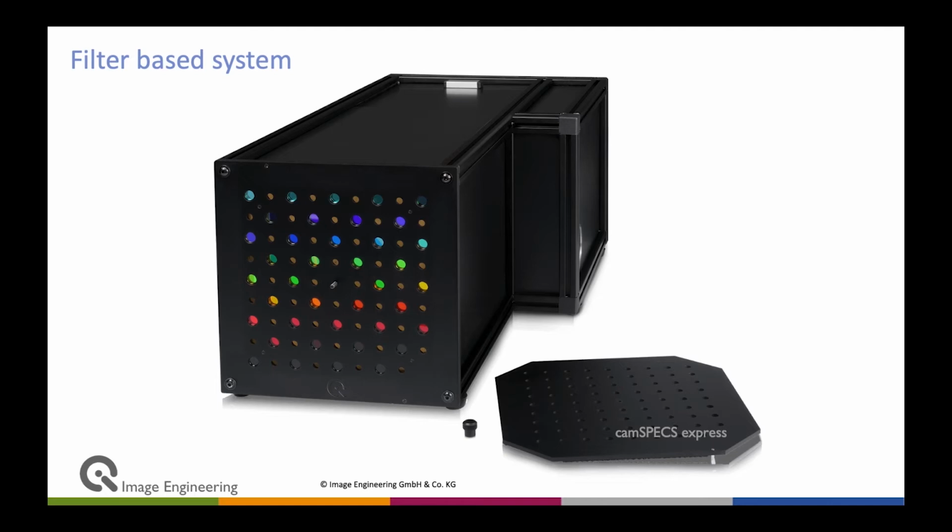The camspecs Express is, as I said, designed with a halogen bulb, and comes with a calibration device so that you can recalibrate every now and then, specifically when you have to change the bulb or if the bulb ages over time. So that's why a production line might not be the best environment for the camspecs Express. It's great for lab and for small volume production lines, but for high volume 24/7, it might not be suitable.